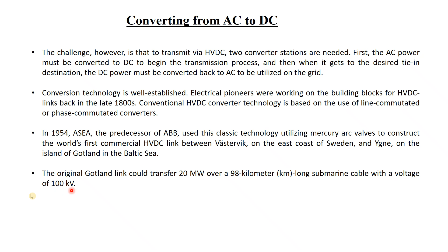Previously, using the mercury arc, that technology had some shortcomings. That is why the power could not be increased beyond 20 megawatt. But with the introduction of SCR, that is the thyristor valve bridge, the power was increased to 30 megawatt, and the voltage was also increased to 150 kV. Obviously, if you want to increase the power, you have to increase the voltage, because increasing the current will result in more power loss, so it is not acceptable.